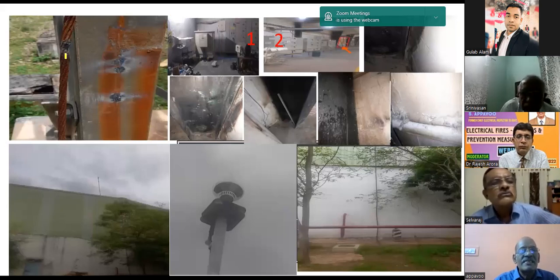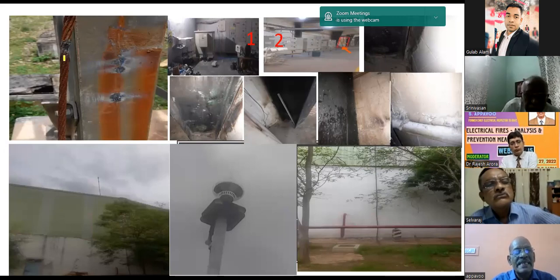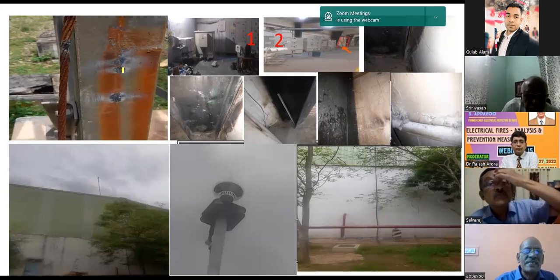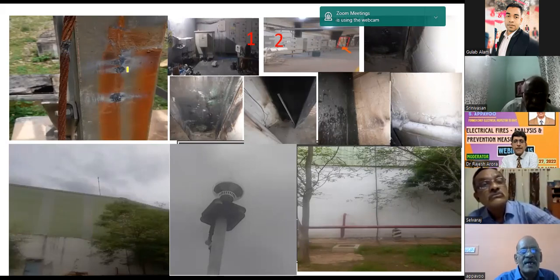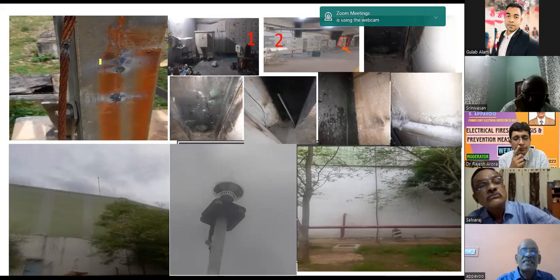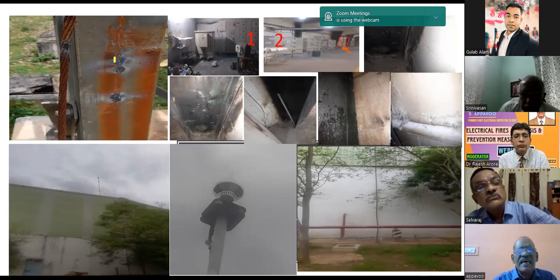And at the 33 kV substation, there was an overhead screen earthing and three lightning arresters. You see the impact of burning of the steel, that is, the stranded steel earth conductor that was attached to this RSJ pole. You can see the burn. I removed it to show the impact of the burn, the melting of the earth wire as well as the RSJ due to the short circuit. It is not due to the lightning. It is due to the short circuiting of the lightning arresters in the supply 33 kV substation after the occurrence of the lightning.